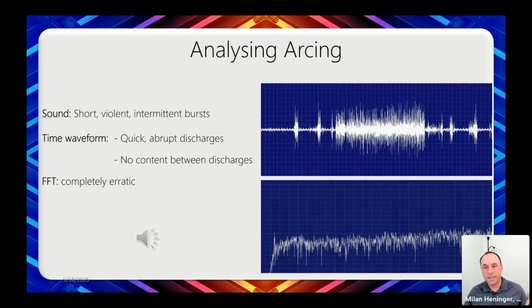The sound tends to be very violent, intermittent bursts. It's aggressive. You get these really abrupt discharges, and you have essentially no content between the discharges, because as it's building up and it flashes over, you get this arc, and then it's building back up and it's flashing over. It can get more and more aggressive to where it does start to sound like a steady, aggressive burning, like you would expect an arc to sound. But because of this effect, we tend not to see anything in the FFT. It just turns into noise.